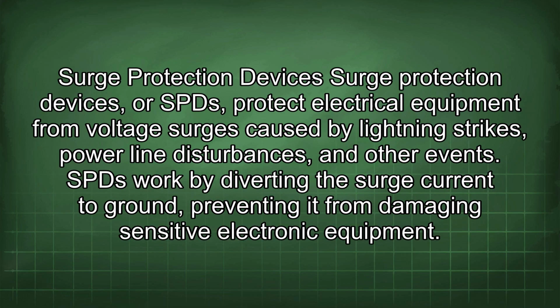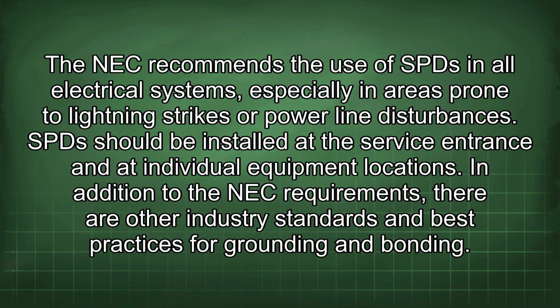Surge protection devices. Surge protection devices, or SPDs, protect electrical equipment from voltage surges caused by lightning strikes, power line disturbances, and other events. SPDs work by diverting the surge current to ground, preventing it from damaging sensitive electronic equipment. The NEC recommends the use of SPDs in all electrical systems, especially in areas prone to lightning strikes or power line disturbances. SPDs should be installed at the service entrance and at individual equipment locations.